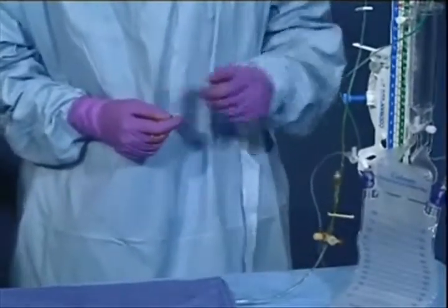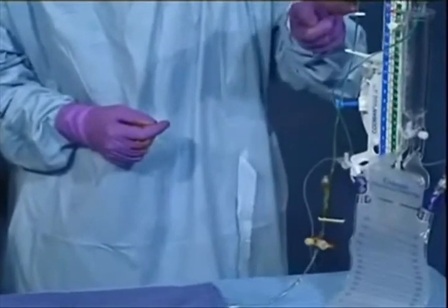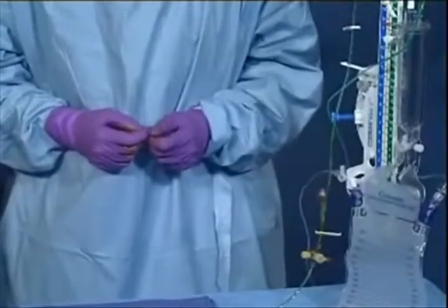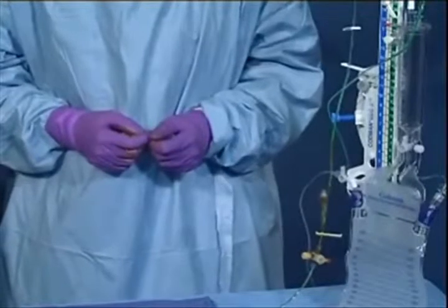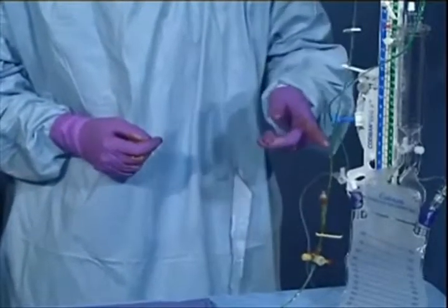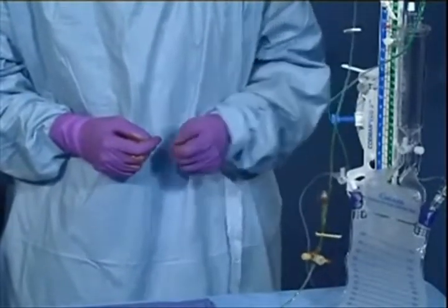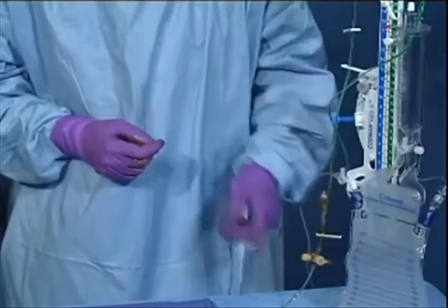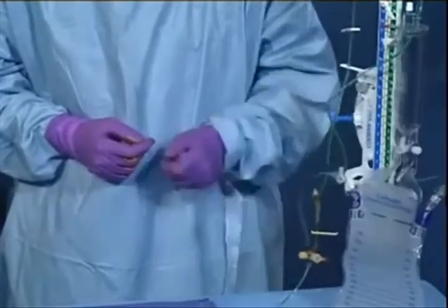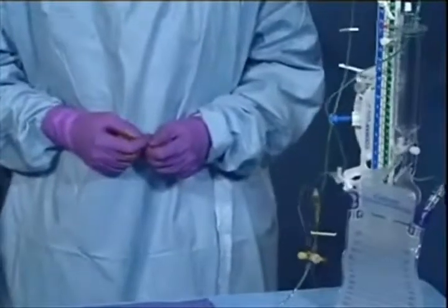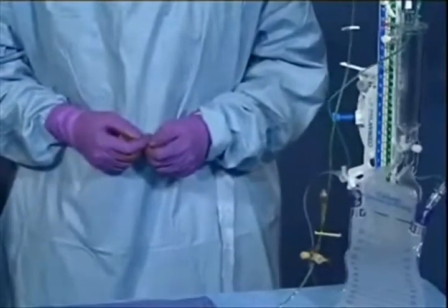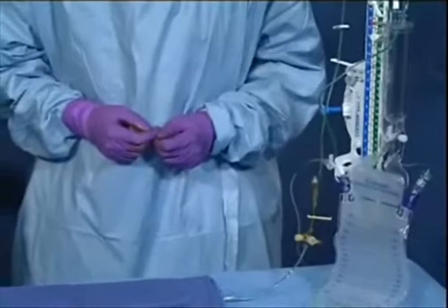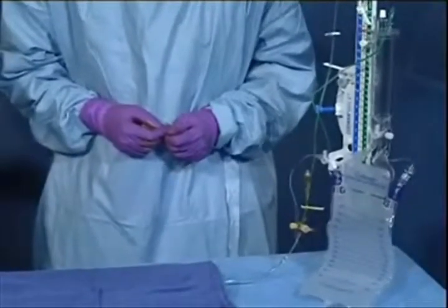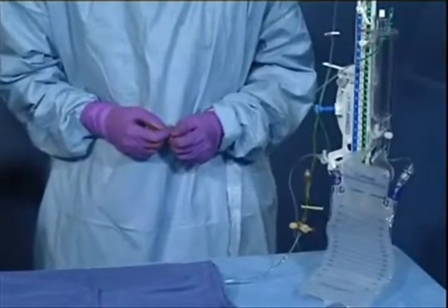Because the tubing is clamped with these slides, whether we inject or aspirate, no fluid will move through this limb of the tubing, and the only route is for fluid to go into or out of the patient. If your system allows, it is highly recommended to monitor ICP during the injection by opening the system to the transducer while keeping the drainage bag closed.